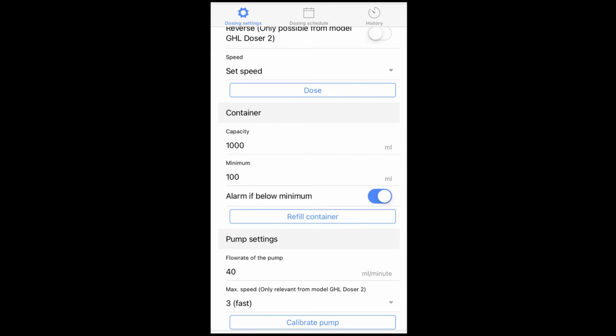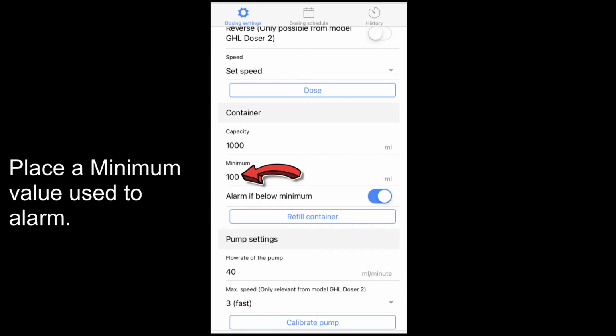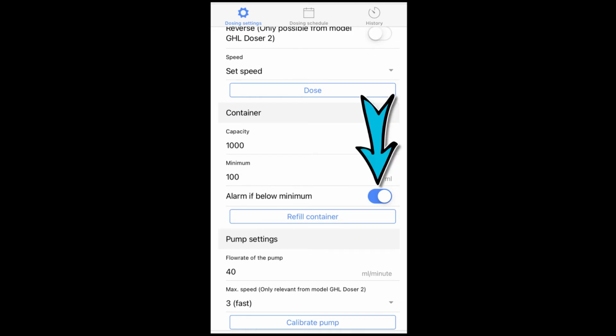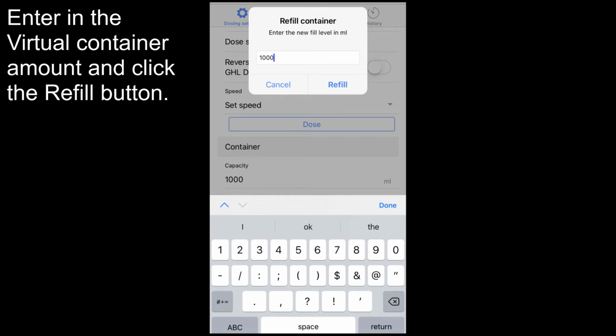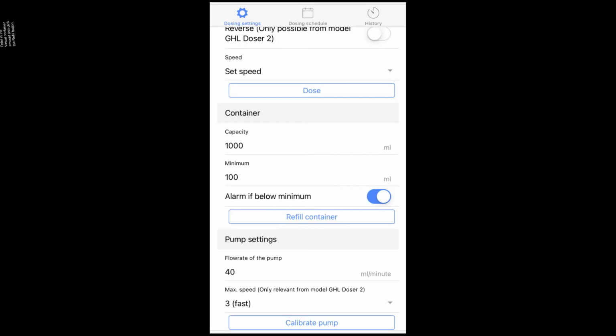By default, when you first purchased your ion director, it was 500. And then choose a minimum value. Make sure the alarm below minimum is enabled, then click on the refill container. Enter in either 500 or 1,000 and then click Refill. This will refill the virtual container, allowing you to monitor how much fluid is being used and alert you when the container is low.